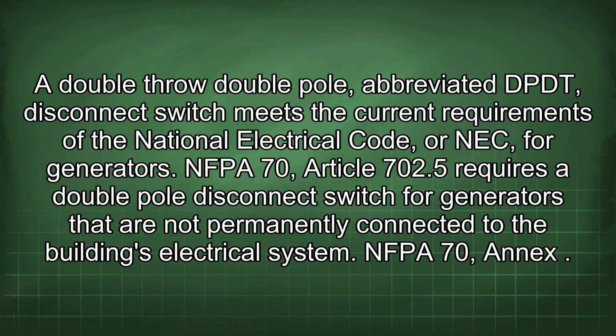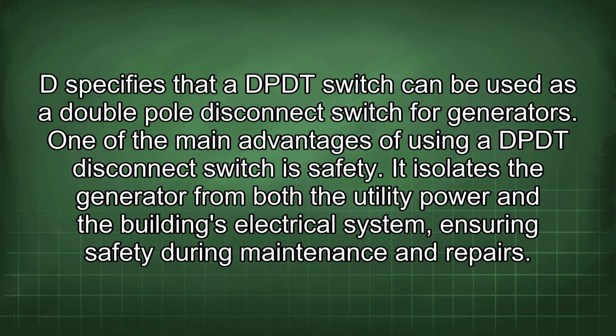A double-throw double-pole, abbreviated DPDT, disconnect switch meets the current requirements of the National Electrical Code, or NEC, for generators. NFPA 70 Article 702.5 requires a double-pole disconnect switch for generators that are not permanently connected to the building's electrical system. NFPA 70 Annex D specifies that a DPDT switch can be used as a double-pole disconnect switch for generators.